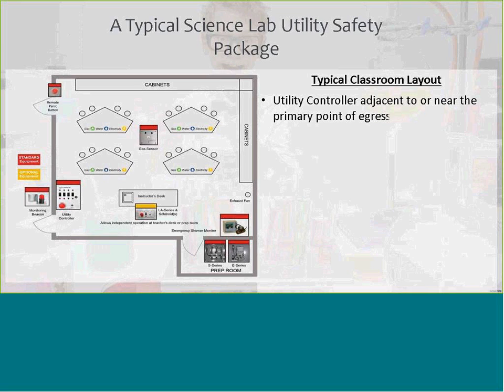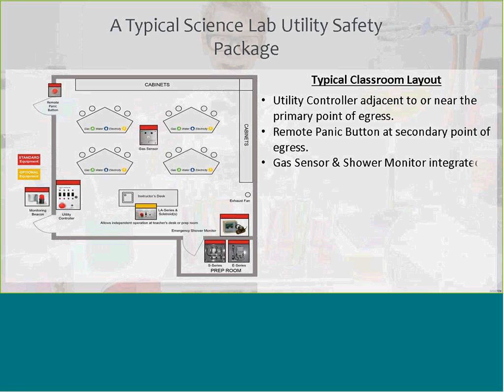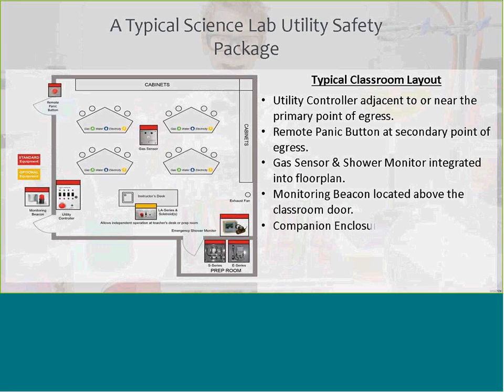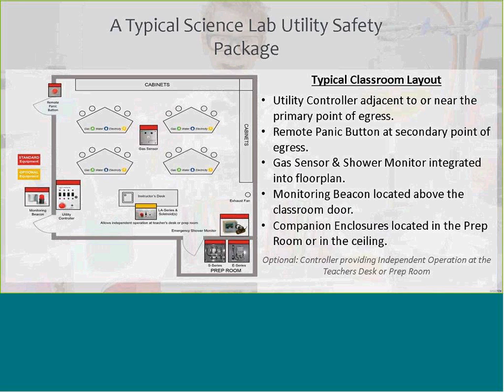In a typical classroom, we're just kind of showing you where you'd want to have your equipment located and which equipment you will have inside a room. Of course, the control panel, you want to locate it at your first egress to the outside. That has the panic button on there. If you have a second egress or a third egress, you want to just put remote panic buttons. That way, if any of the doors are blocked due to fire or something, you have other ways of shutting it down through remote panic buttons. Remote panic buttons can be either maintained or momentary, depending on what type of system you have. Usually momentary is enough just to break the signal to the control panel to shut everything down.